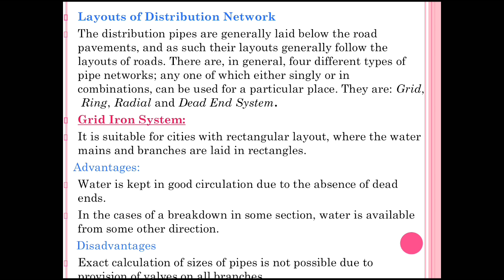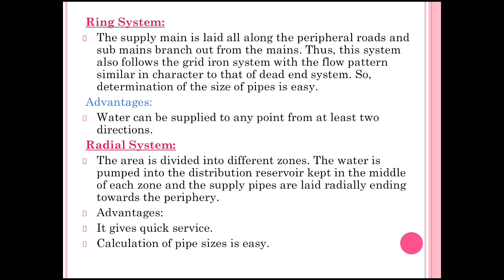The first type is the grid iron system. It is suitable for cities with a rectangular layout where the water mains and branches are laid in rectangles. Advantage: water is kept in good circulation due to the absence of dead ends; in cases of a breakdown in some section, water is available from another direction. Disadvantage: the exact calculation of the size of pipes is not possible due to the provision of valves on all branches. The second is the ring system — the supply main is laid along peripheral roads and sub-mains branch out of the mains, following a flow pattern similar to the dead-end system, making determination of pipe size easier.